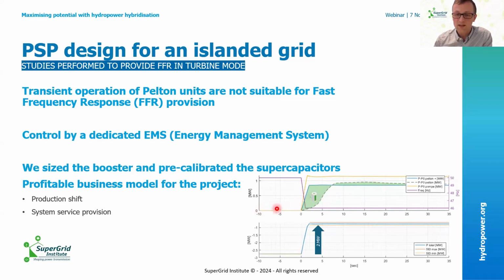And simultaneously, you can see the pump response in yellow, which is 1,200 kilowatts and, being variable speed, is acceptable for the 2-second response required for fast frequency mechanisms.